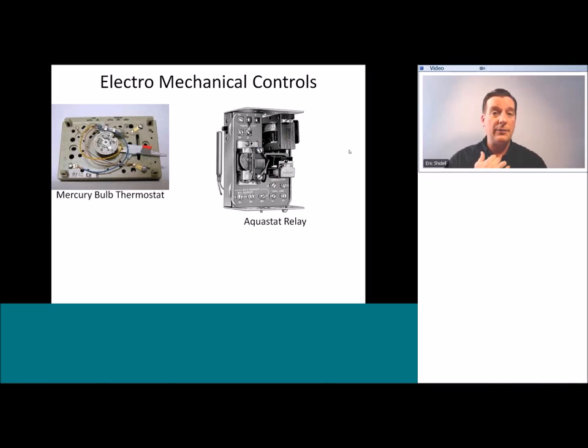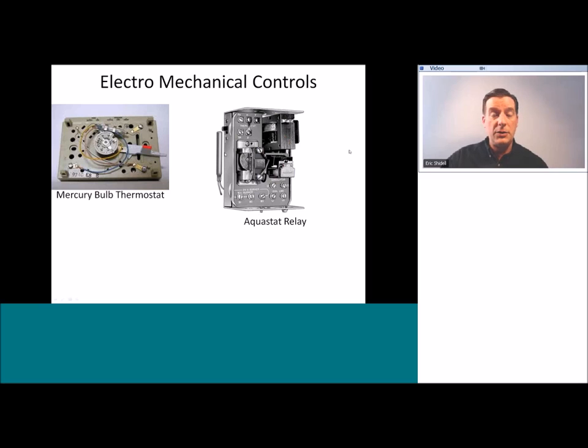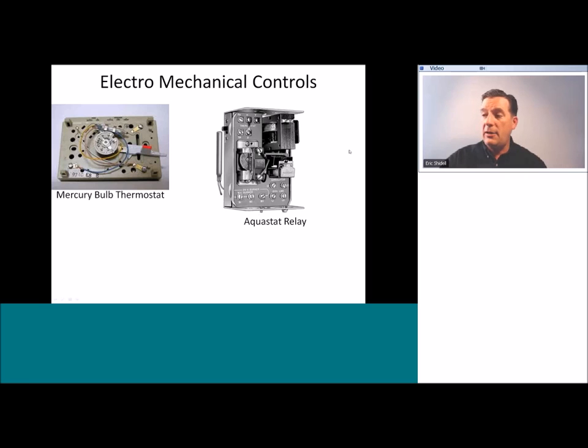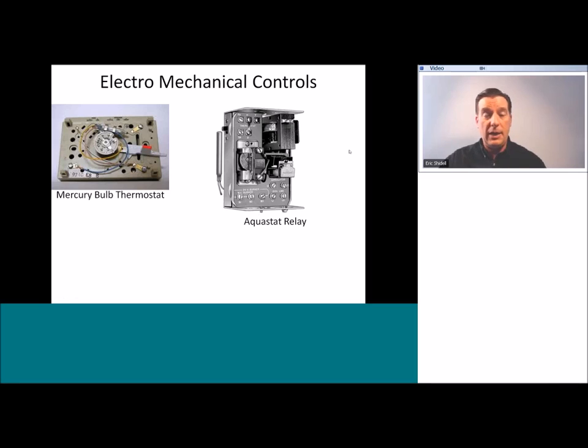The aquastat relay boiler control is another common electromechanical example. Here I've got a temperature sensitive element, just like our water heater control, but now instead of physically opening and closing a gas valve, it opens and closes a set of electrical contacts, which will then power open or power close a gas control.